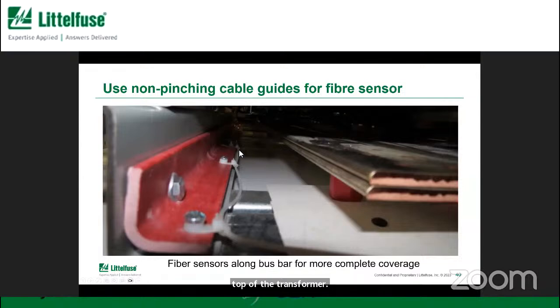Now the fiber sensor, like I mentioned, is quite long. One of the common ways to use it is to put it down beside the bus bar. So this would be able to see a fault anywhere down the line. If you have a lineup of switchgear where your bus bar is 5 meters long or 8 meters long, this is an ideal spot to put the fiber.